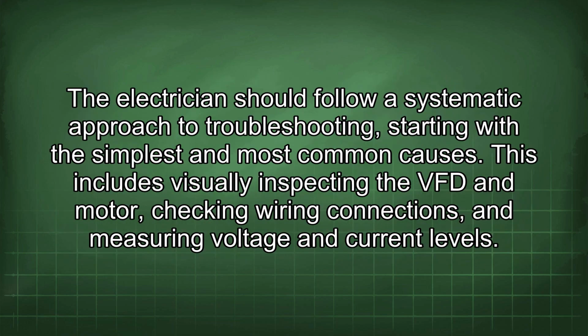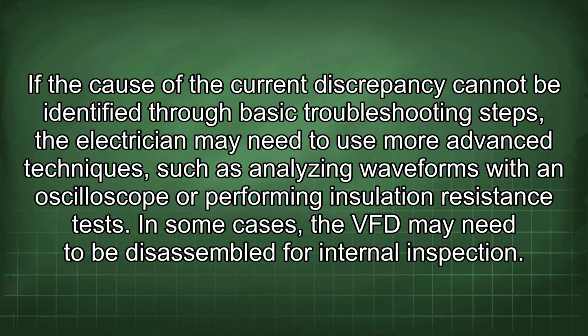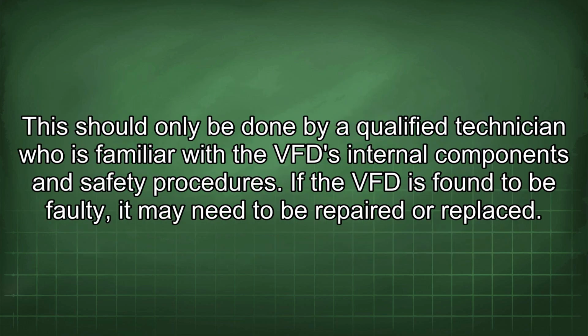The electrician should follow a systematic approach to troubleshooting, starting with the simplest and most common causes. This includes visually inspecting the VFD and motor, checking wiring connections, and measuring voltage and current levels. If the cause of the current discrepancy cannot be identified through basic troubleshooting steps, the electrician may need to use more advanced techniques, such as analyzing waveforms with an oscilloscope or performing insulation resistance tests. In some cases, the VFD may need to be disassembled for internal inspection. This should only be done by a qualified technician who is familiar with the VFD internal components and safety procedures.